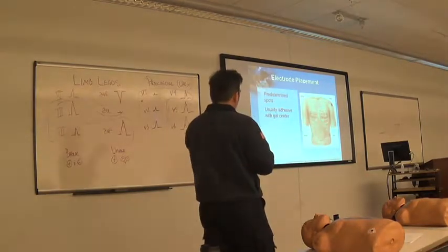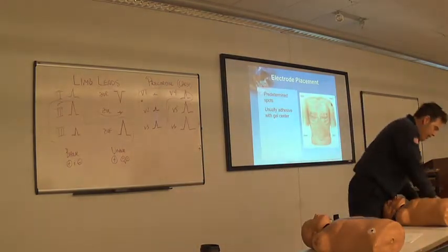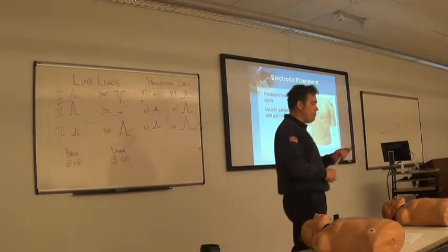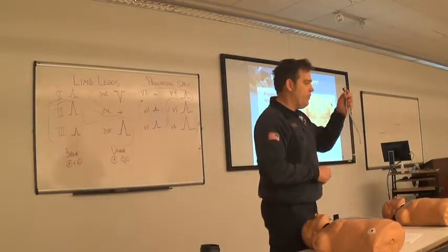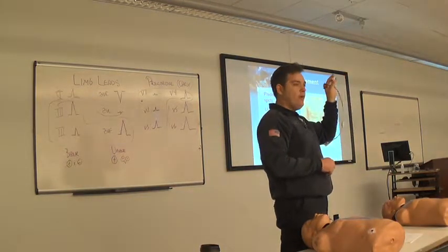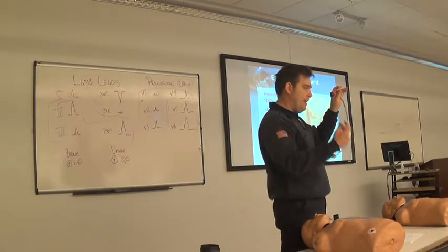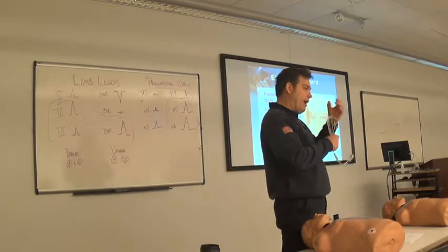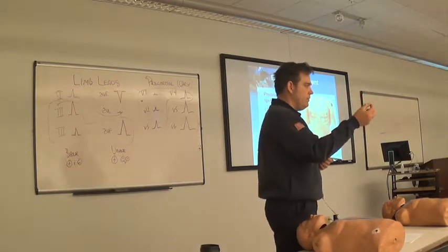Electrode placement, predetermined spots, we talked about that. One thing that's worth mentioning here is that, depending on the service that you work for and the volume of calls that you do, a lot of people like to pre-connect the electrodes to the wires. Unless you're running a couple of 12 leads, like boom, boom, boom, all the time, the minute you take them out of their package, that medium begins to dry out.